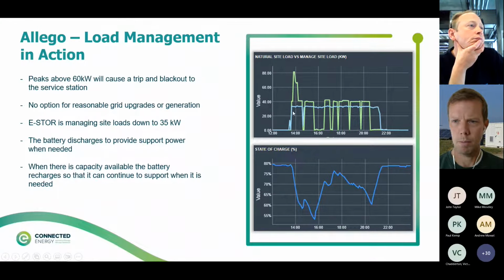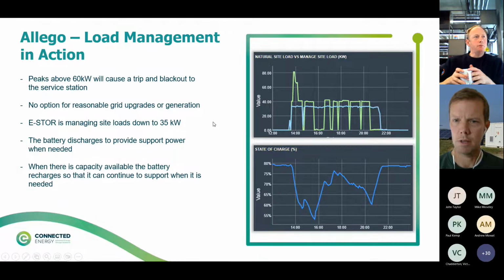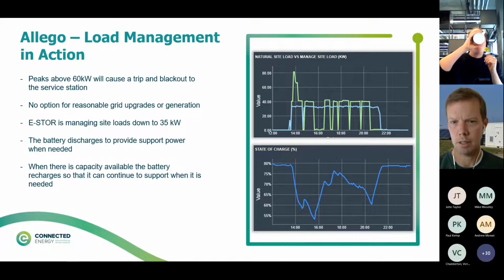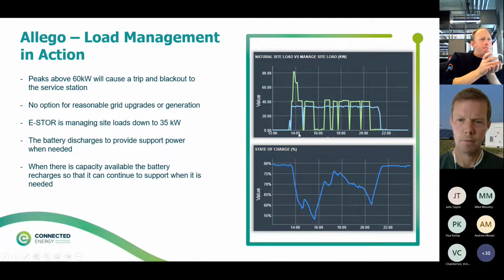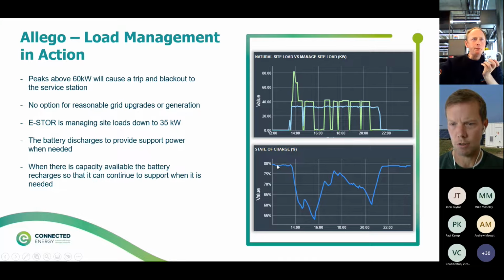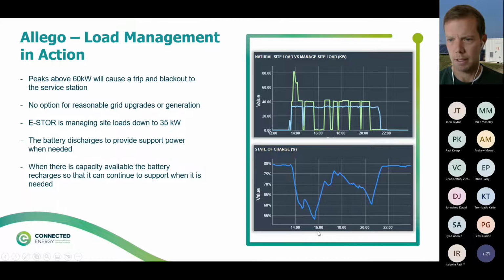So what we're doing is we're maintaining a 35 kilowatt usage by monitoring the EV charging demand and providing the battery power into that EV demand as and when it's required. So you can see the state of charge of the battery, we're discharging out into the site, offsetting this peak, and then we're charging up again here when there's no demand, and then discharging out again. So this is real-time data that we can monitor, and we can verify that we are maintaining this 35 kilowatt constraint.